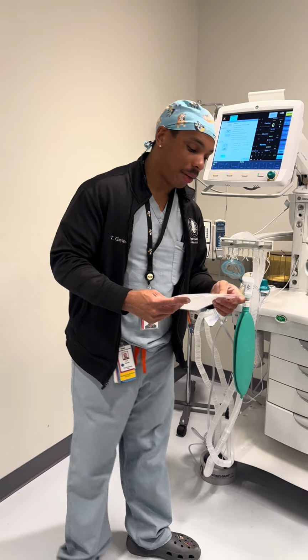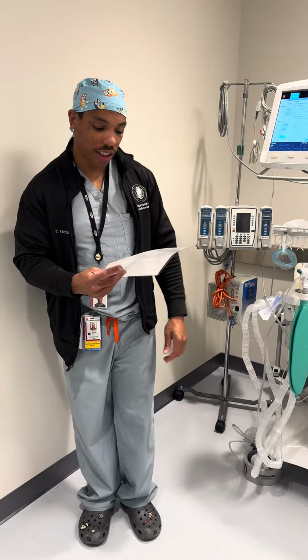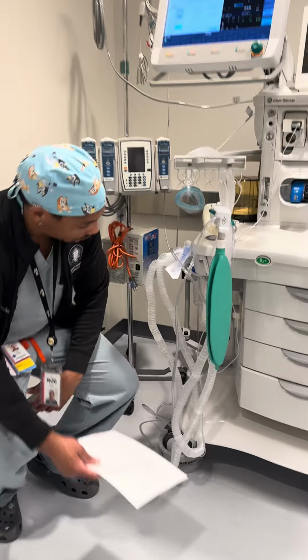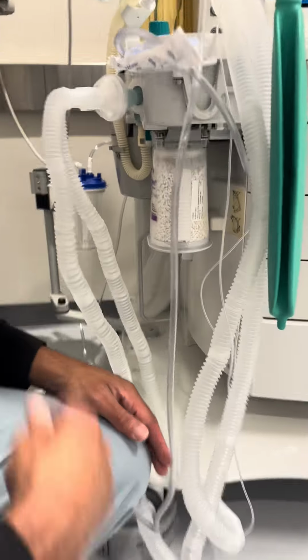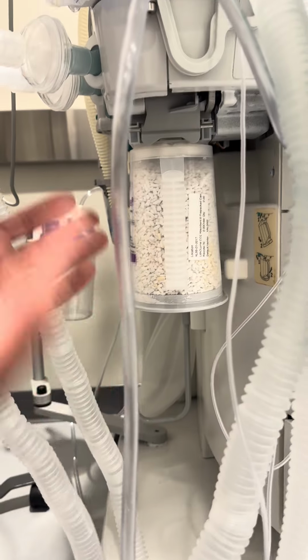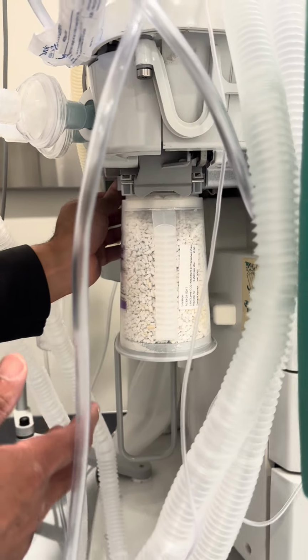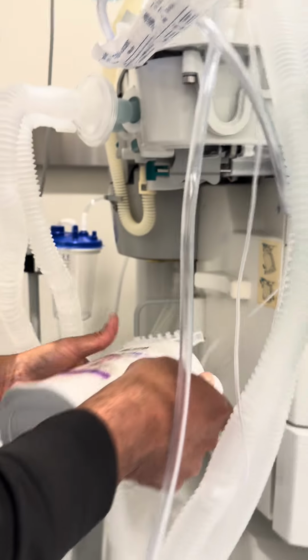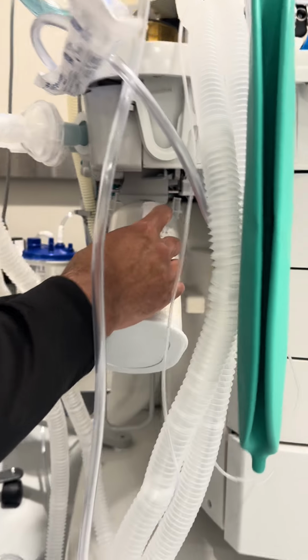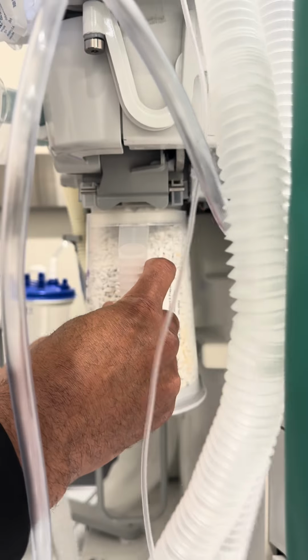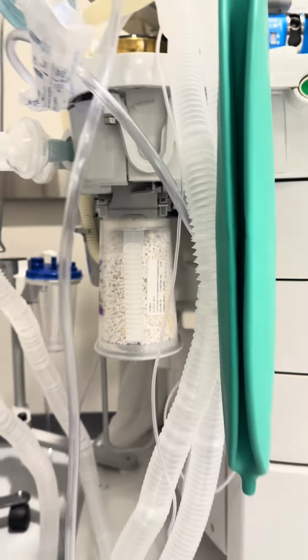The 6th step is going to be check and ensure Sodasorb is present and not exhausted. So we're gonna come over here, look at the Sodasorb. You're gonna tell me that it's not exhausted, because if it's not purple, it's not exhausted. And then you're gonna take it out, make sure it's good, put it back in. And you hear that click, it's good to go. Okay.